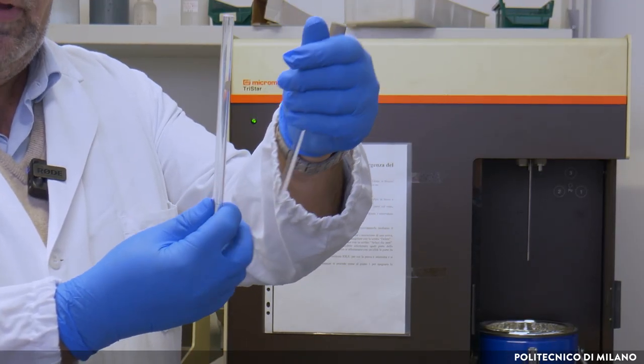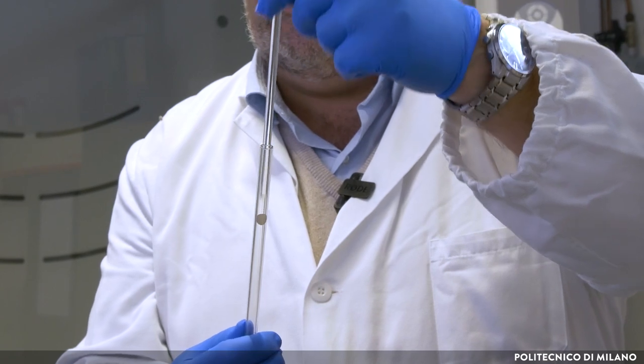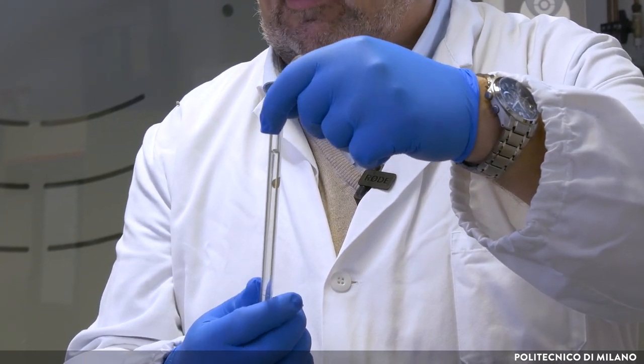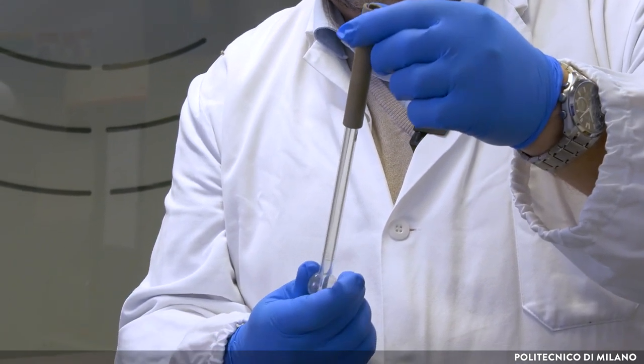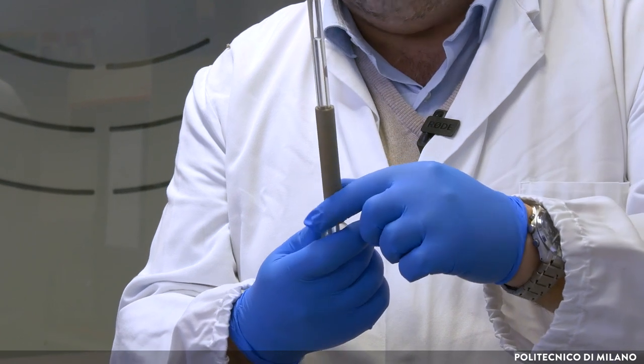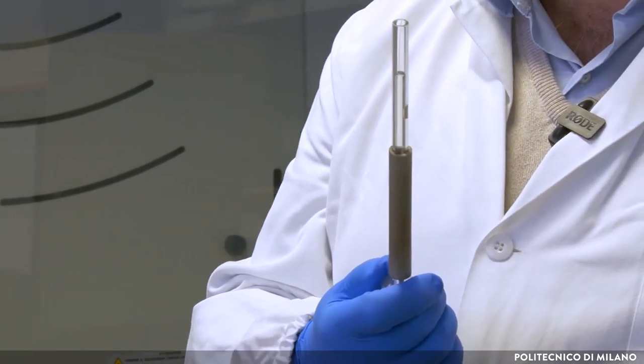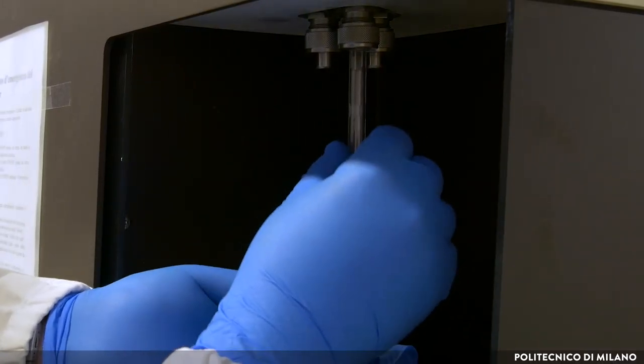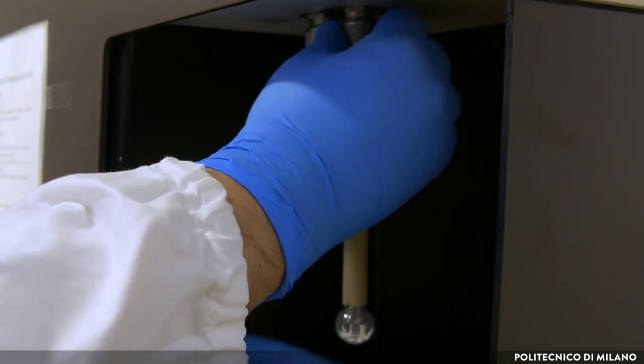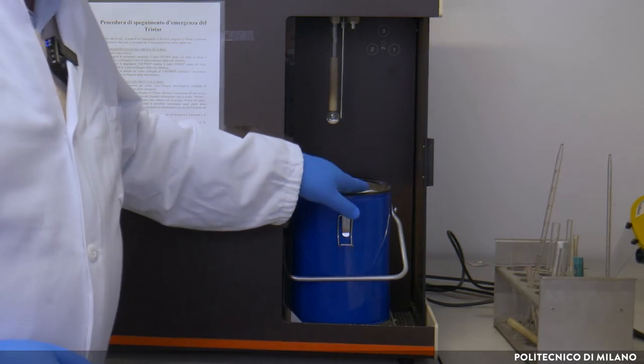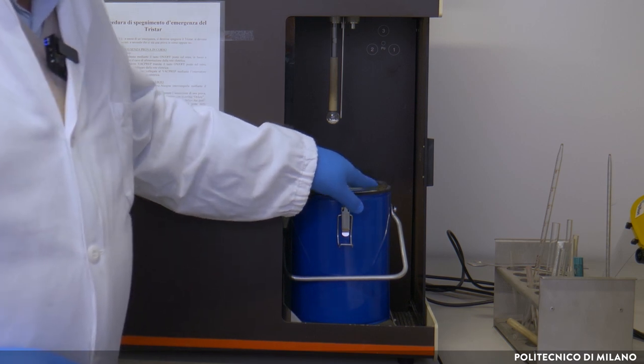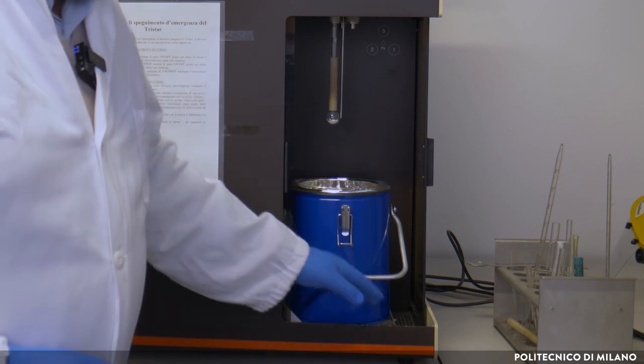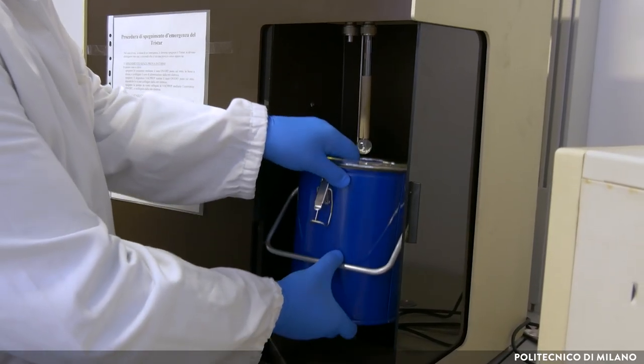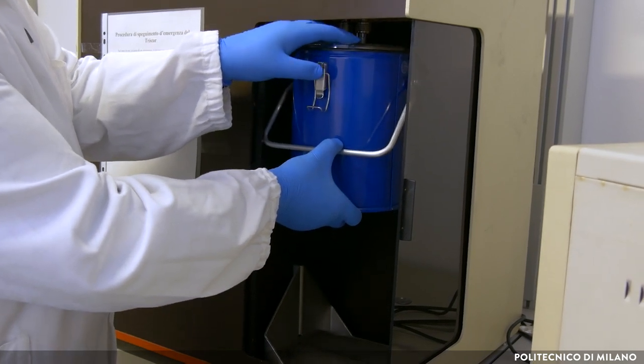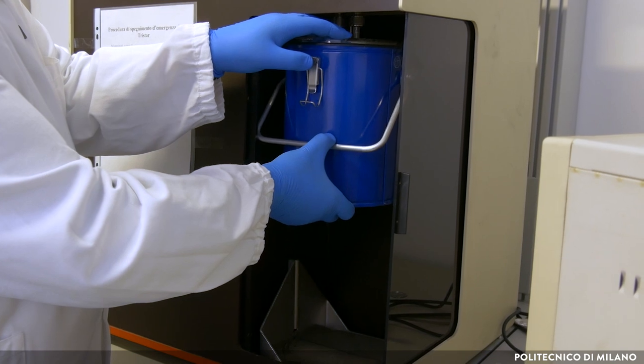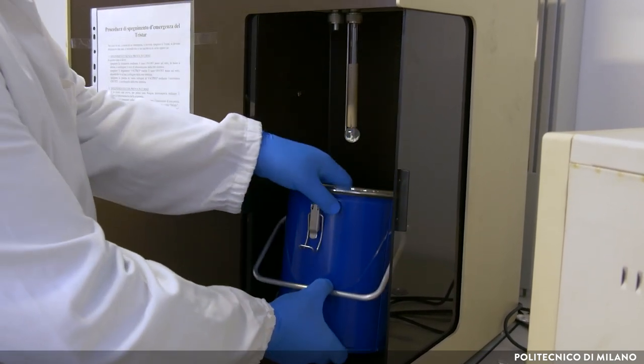In the second phase, we insert a glass rod in the sample holder to reduce empty volumes. A plastic coating is inserted on the outside that helps in maintaining isothermal conditions during the experiment. Finally, the sample holder is connected to the instrument. The dewar is filled with liquid nitrogen, where the sample holder will be immersed. Since physisorption requires very low energy, it is necessary to maintain the system at very low temperature. The liquid nitrogen is at 77 Kelvin.